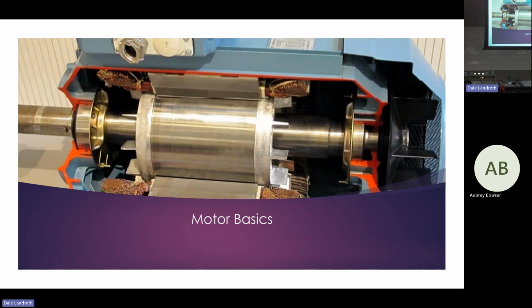So if we got a good understanding of this, we can start troubleshooting and doing things that most people don't know. Most people don't know this, and when I say most people don't know this, I didn't know this. I had a basic understanding, but like I've said 1,000 times, if we understand motors, how many times do we work on motors? Every day, every day we work on motors. I don't care if it's a 2 horsepower motor or a 1,000 horsepower motor. If you can become competent on troubleshooting motors, you just made a name for yourself, because most people don't know how to do it, and they condemn motors when they don't need to be condemned. So how many have ever condemned a motor that didn't need to be condemned?